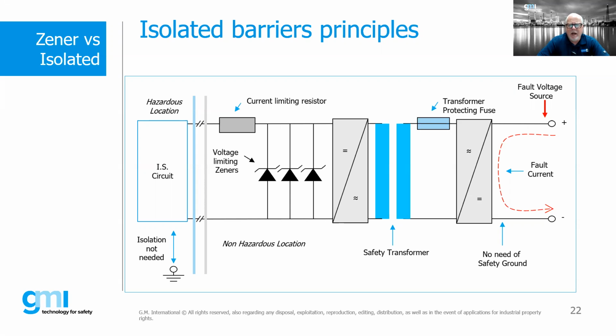That's the big difference with an isolated barrier - notice at the bottom, that fault condition stays in the general non-hazardous area. There is no requirement for a safety ground with a galvanically isolated barrier. That's really the big difference between a Zener diode type barrier and a galvanically isolated barrier: the requirement of the safety ground.